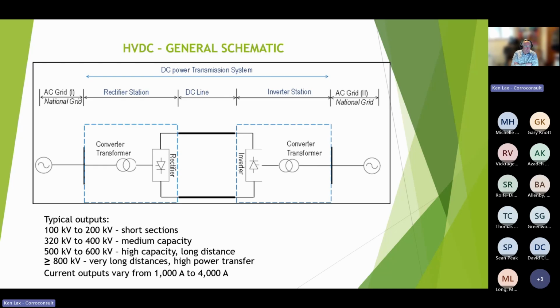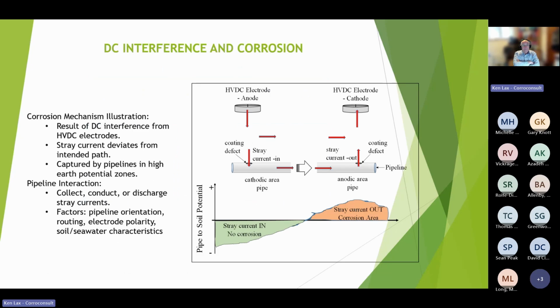Some typical outputs for these systems would be 100,000 to 200,000 volts for short sections, because you don't get much in the way of losses; 320 to 400,000 for medium capacity; 500 to 600,000 for high capacity; and more than 800,000 for very long distances and very high power transfer. Current outputs will vary, roughly between 1,000 and 4,000 amps. So you're dealing with quite big numbers here.